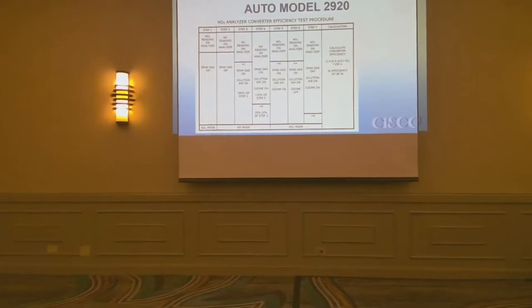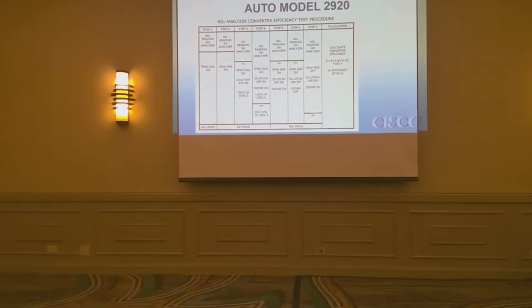These steps here are programmable in time. You have an input that you check for stability on the analyzer, time in. All seven steps in our training center take about 10 minutes to walk through. That is except for step four. We have logic in the PLC that says, look for this value, and we'll get down to about 15% of this value here, then shut the step off. And the PLC will automatically set the right time for you. If you go too long, you'll get down below 10%. If you don't go long enough, you will get down to 20%.